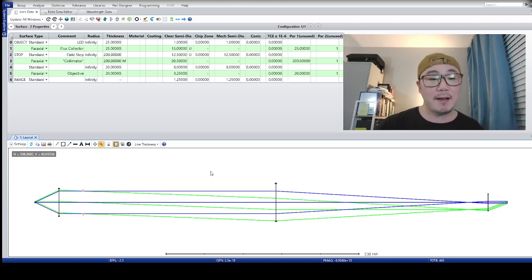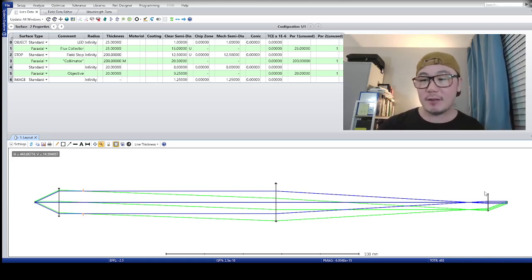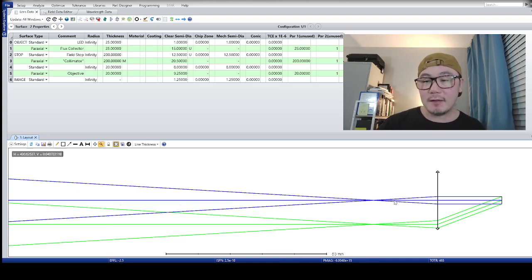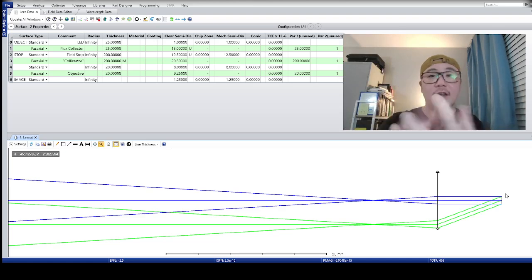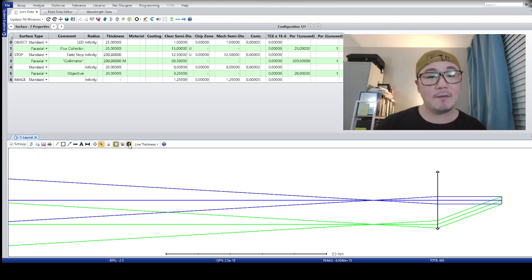These are conjugate planes. And by the way, this is called a Köhler illumination setup. In this setup, we purposely project the source into the back here. If the source has some structure to it, some hot spots and cold spots, then all of that is projected to the back here. But guess what? When they come out through the objective lens, they homogenize at the specimen plane, the sample plane. You see, this axial ray hits here, the off-axis ray gets bent, it's here, and many such rays just come together and superpose at the sample plane, and that is the homogenization effect of Köhler illumination.